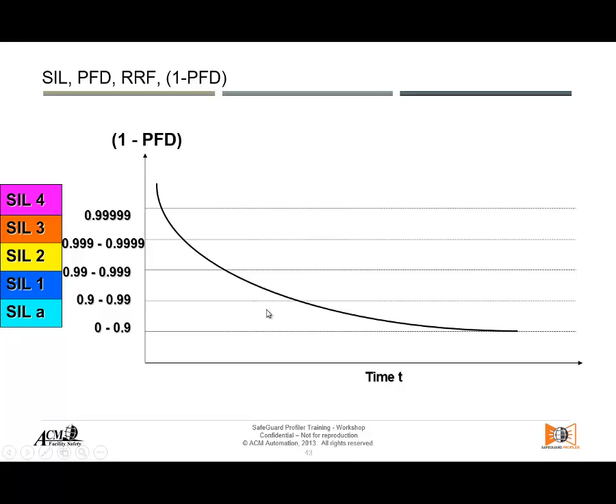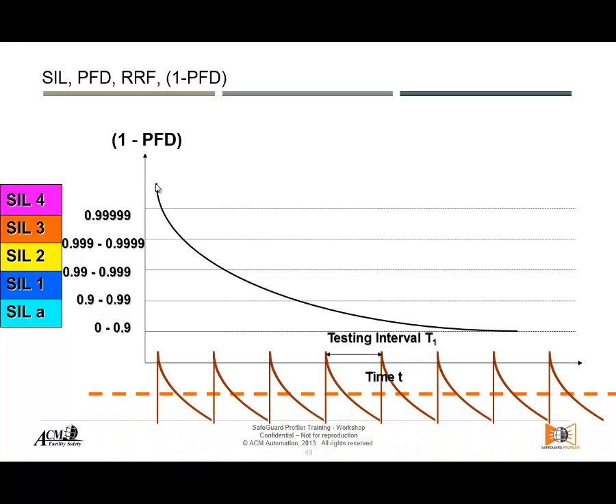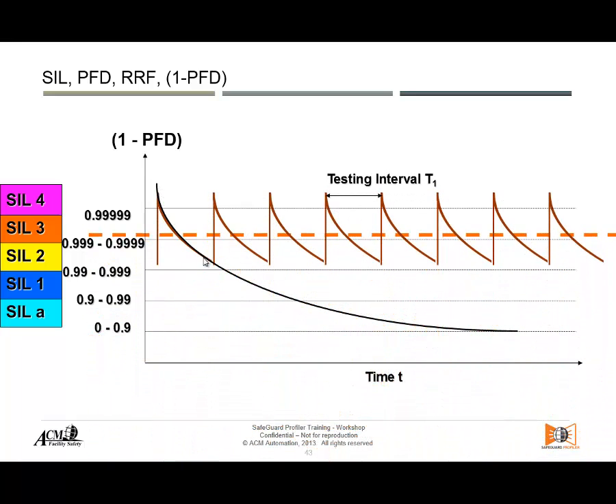This is what we've been talking about — all these tables about the relationship between probability of failure, safety availability, or reliability of the safety instrumented function. So 1 minus PFD, that would be with respect to reliability. At the beginning of time, we consider the system to be very reliable, high reliability. And as time goes by, its reliability decreases. This is another way of looking at, in time, what happens to your equipment with respect to working when required.